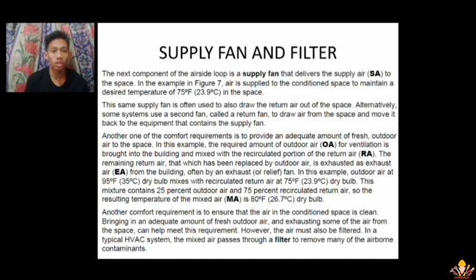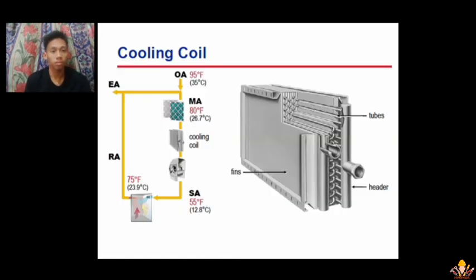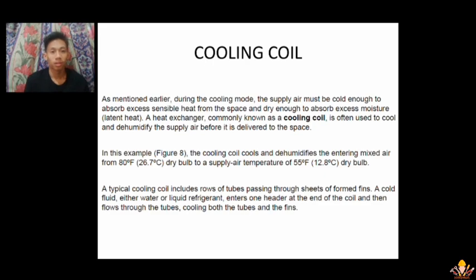However, the air also must be filtered in a typical HVAC system. The mixed air passes through a filter to remove many of the airborne contaminants. Another component is the cooling coil. As mentioned earlier, during the cooling mode, the supply air must be cold enough to absorb excess sensible heat from the space and dry enough to absorb excess moisture. A heat exchanger, commonly known as a cooling coil, is often used to cool and dehumidify the supply air before it is delivered to the space.